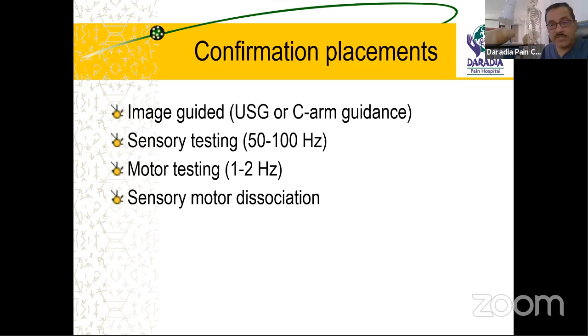So this is also called the sensory motor dissociation. So what is sensory motor dissociation? That means when we are delivering the current at a certain voltage at 50 hertz and we see that there is a stimulation, then you double the current. Say for example, you are stimulating at 0.5 volt, and now you are giving the current at 1 volt, and still the inadvertent motor fibers are not stimulated. This is called sensory motor dissociation. That means our needle is close to our target nerve, but not close to other inadvertent nerves which might be around. So you give double the current at where we got the sensory stimulation, and you see that there is no inadvertent stimulation. Then you confirm that your needle placement is proper.